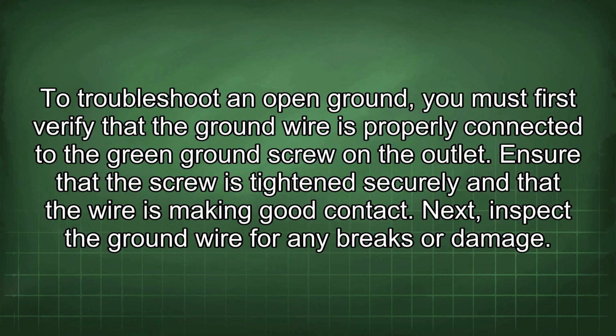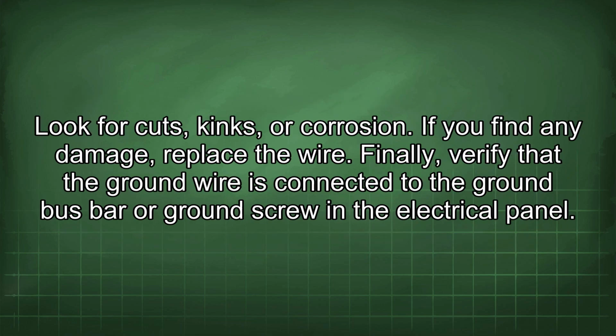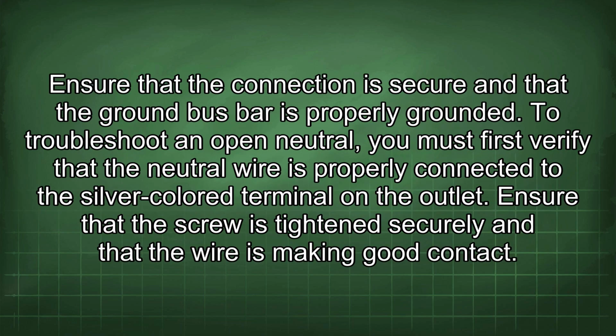To troubleshoot an open ground, you must first verify that the ground wire is properly connected to the green ground screw on the outlet. Ensure that the screw is tightened securely and that the wire is making good contact. Next, inspect the ground wire for any breaks or damage. Look for cuts, kinks, or corrosion. If you find any damage, replace the wire. Finally, verify that the ground wire is connected to the ground bus bar or ground screw in the electrical panel. Ensure that the connection is secure and that the ground bus bar is properly grounded.